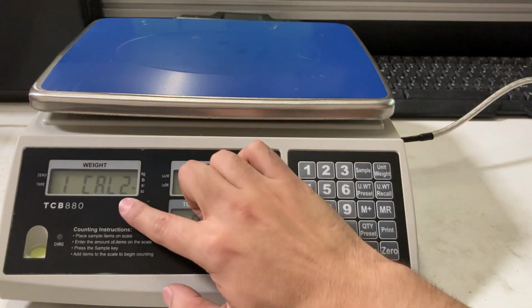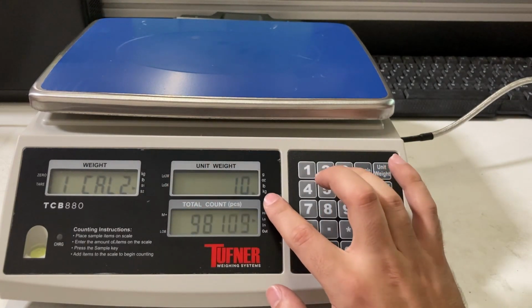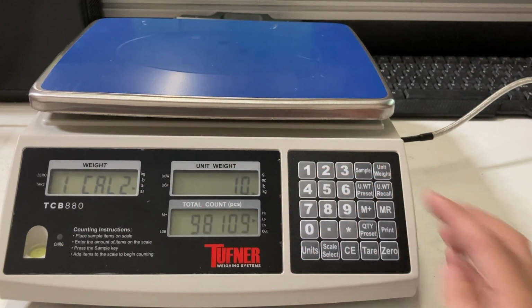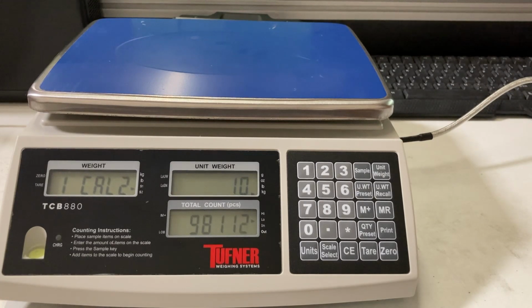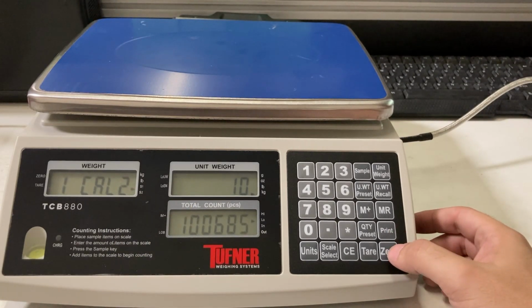Now you see 1 cal 2, and you'll see 10 here - that is 1/3 of the maximum capacity set. I said 30 kg is max capacity, so now I'm using a 10 kg. You'll see how the number went up - don't worry about what number it says, but 10 kg is on there.